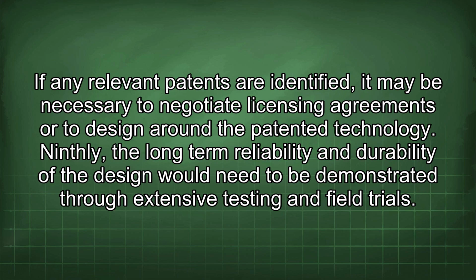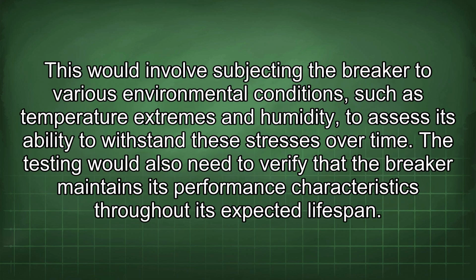testing and field trials. This would involve subjecting the breaker to various environmental conditions, such as temperature extremes and humidity, to assess its ability to withstand these stresses over time. The testing would also need to verify that the breaker maintains its performance characteristics throughout its expected lifespan.